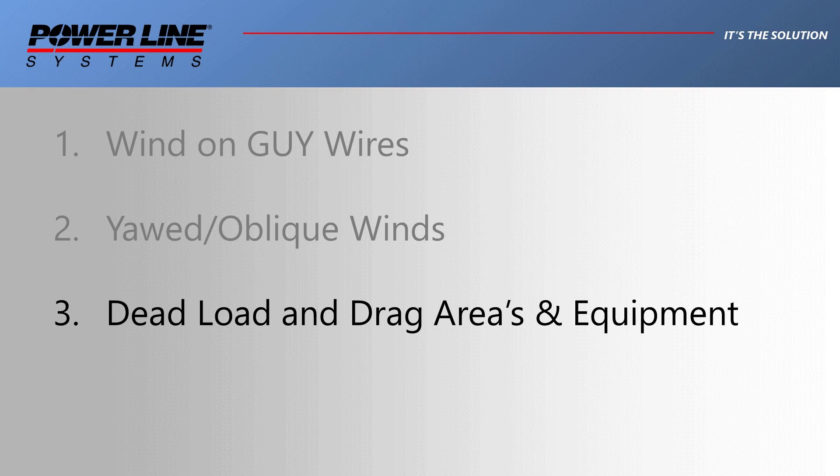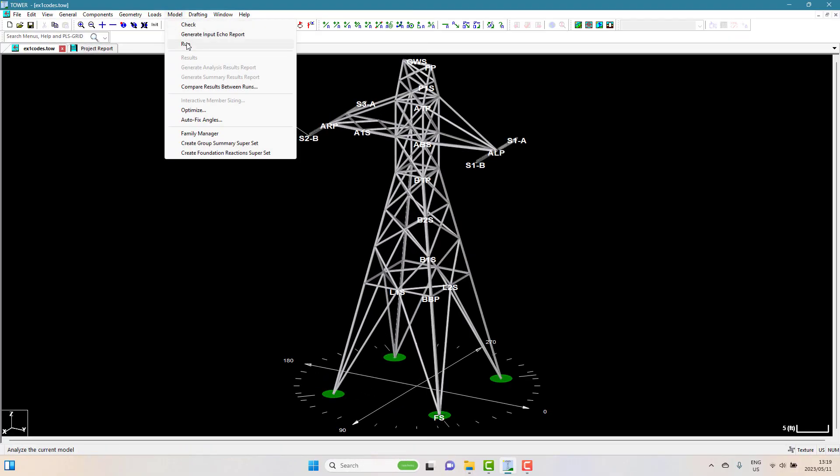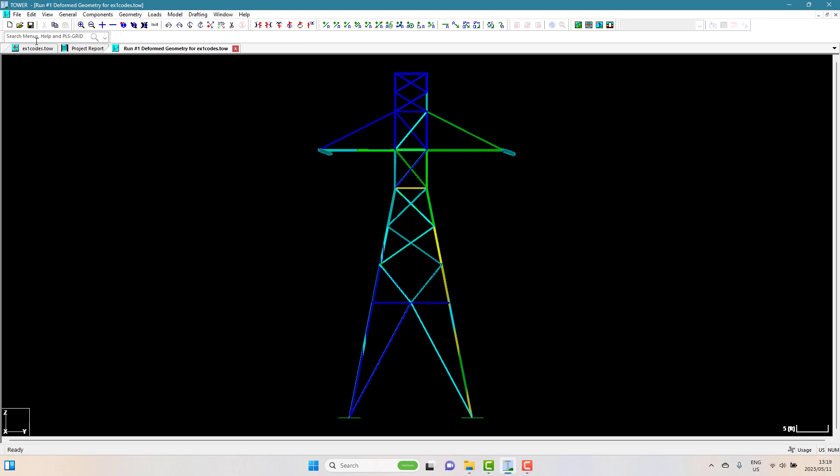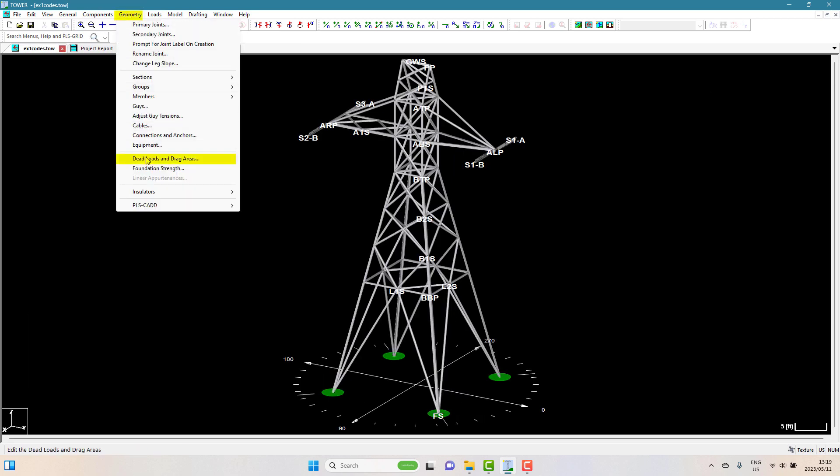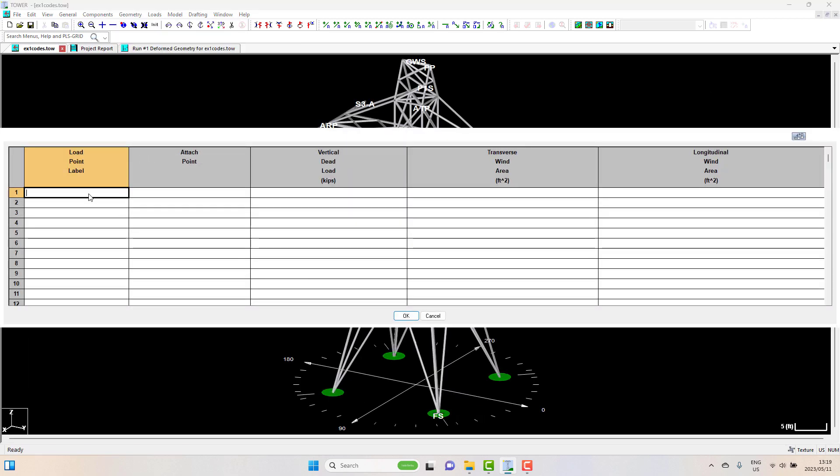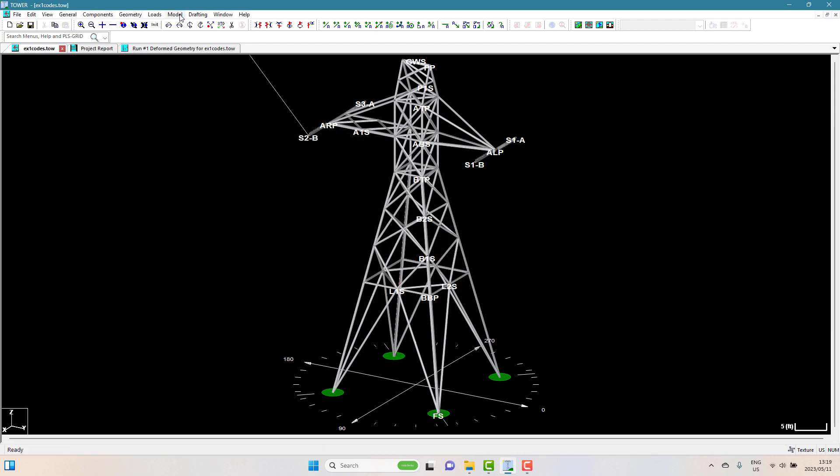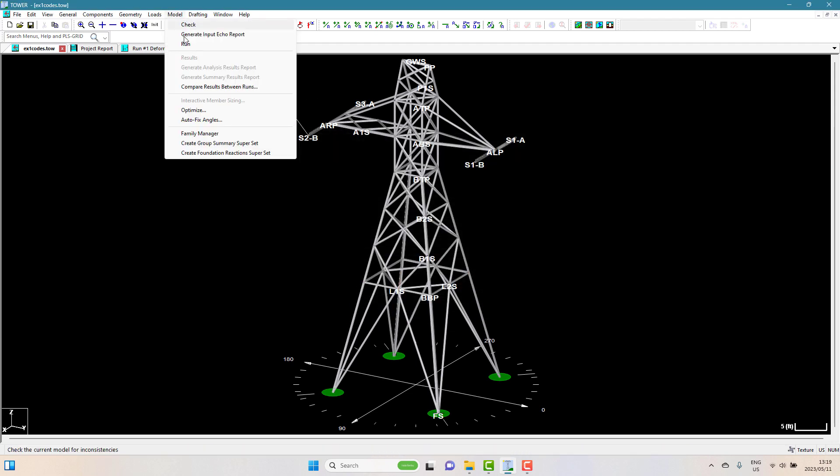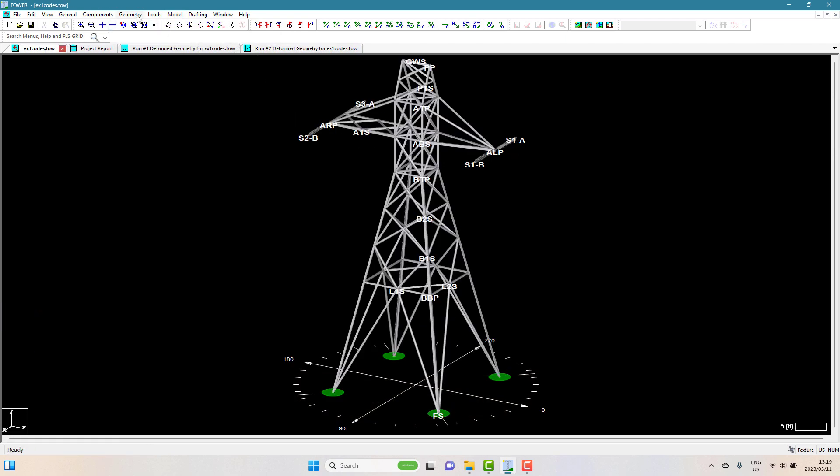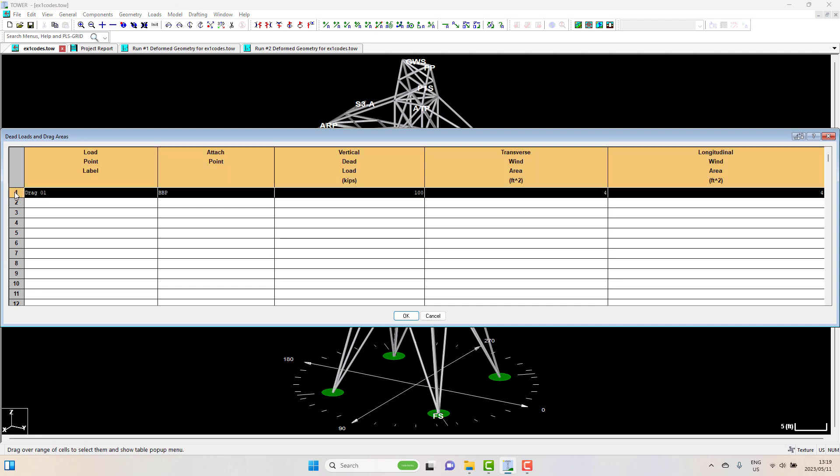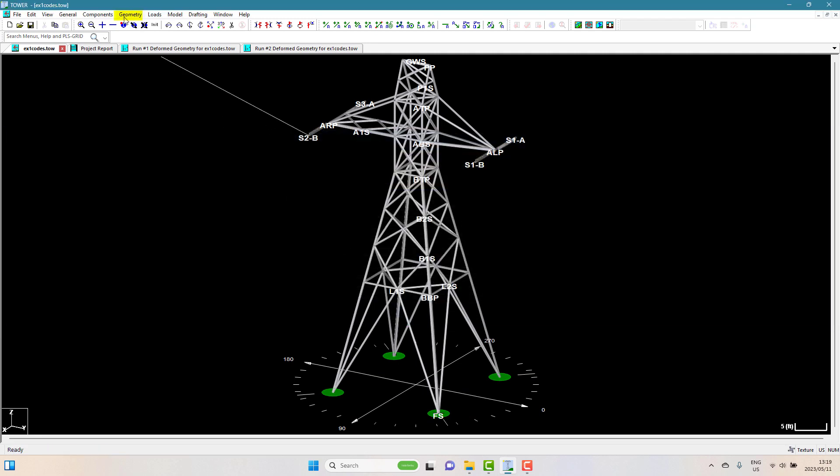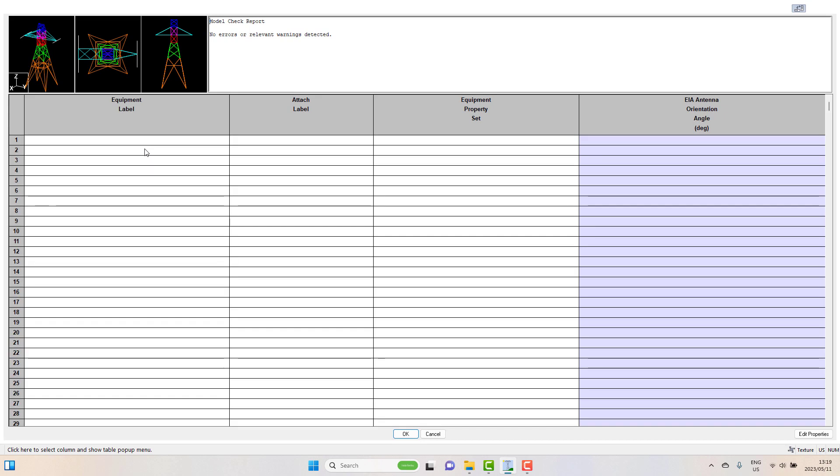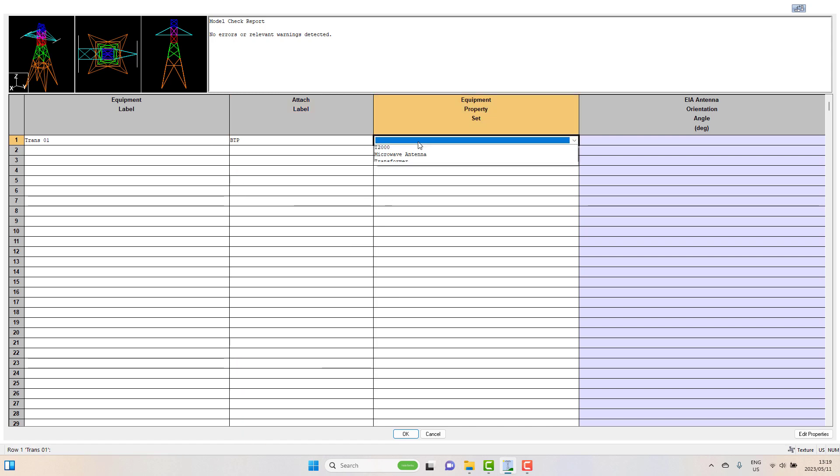The final topic to mention is that tower also allows you to add wind areas or drag areas to any joint of a tower for things that are not modeled, but can in fact bring loading onto the tower. You could use this to simulate signage, ladders, cable trays or anything of that nature. These are applied to any joint of the tower by using the geometry, dead loads and drag areas dialog. You will see that nothing visual is added to the model. If you wanted something visual to be added to the model, for example a piece of equipment, we have another menu option to allow that. It is a very similar approach in the way that the loads are calculated, but in this case it will leave a visual representation on the screen.